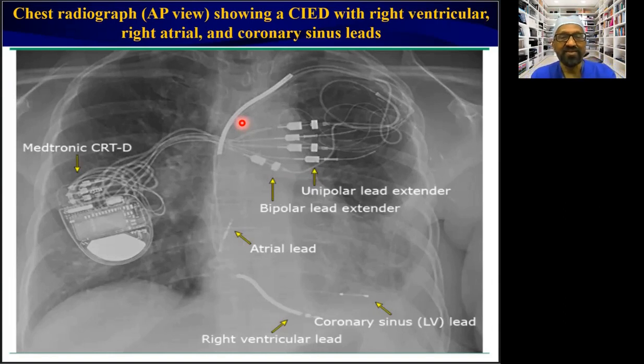This picture shows a patient who had breast surgery on the left side and had an implantable cardiac resynchronization therapy device on the left side. Because of the breast surgery, it had to be shifted to the right side, with lead extenders attached to the implanted device connecting to leads already in the cardiac chambers. We should be aware that we might encounter such patients and not be confused by the many leads — extender leads have been used and only the cardiac device has been shifted to the right side of the chest.